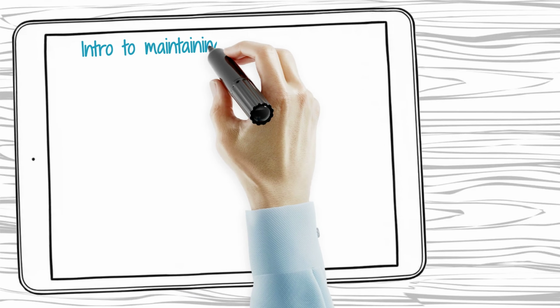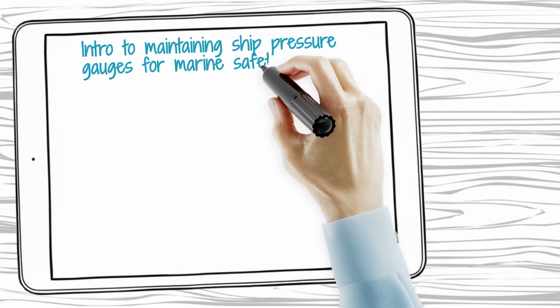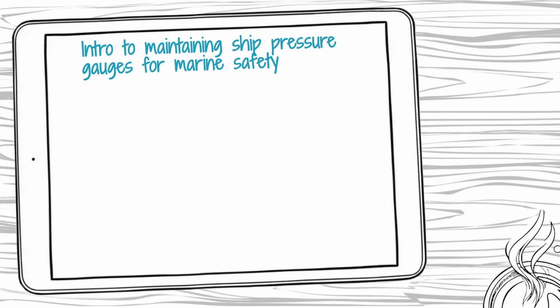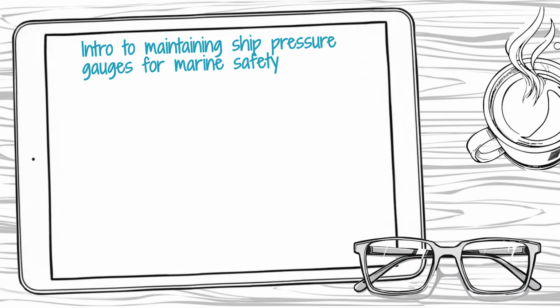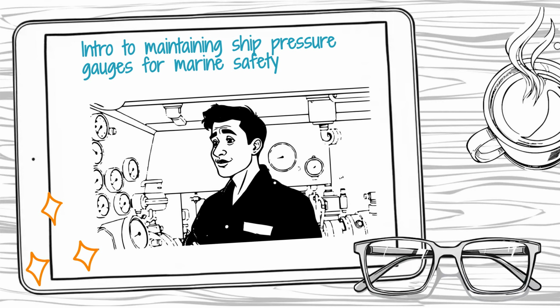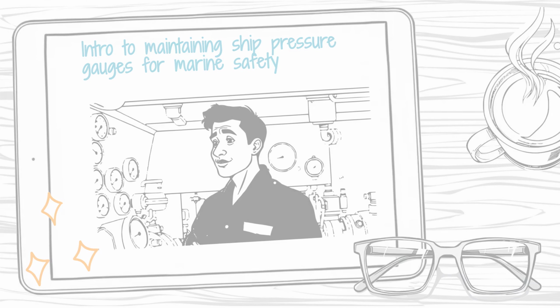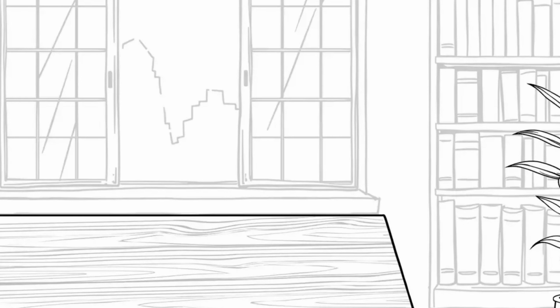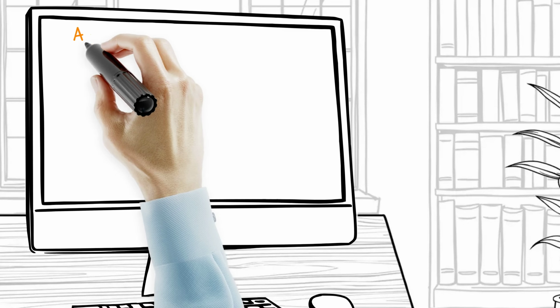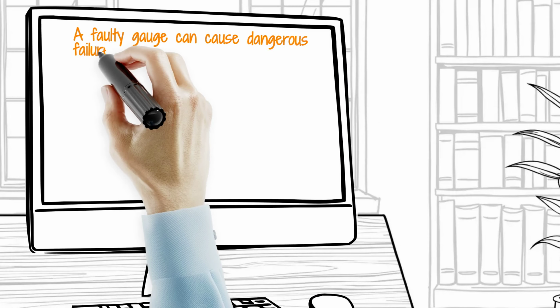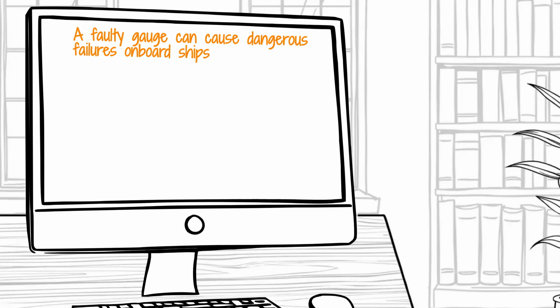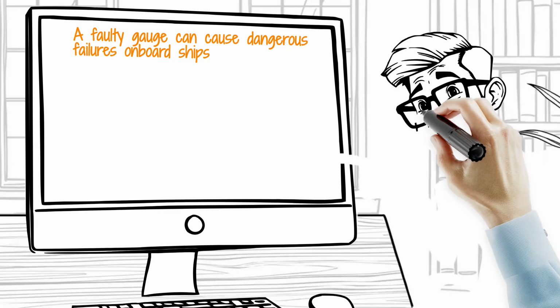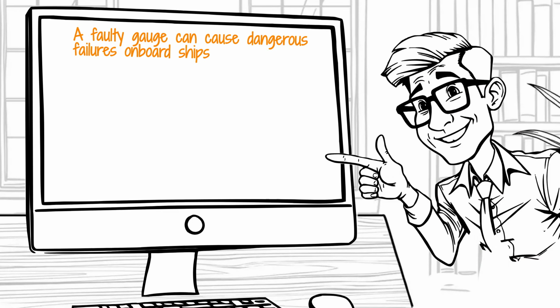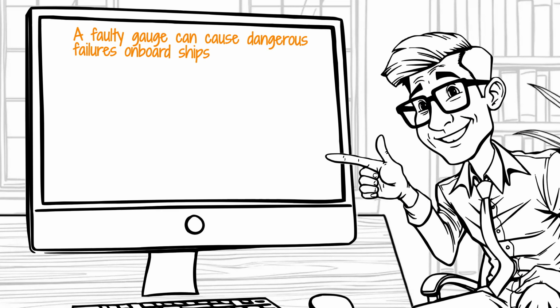Maintaining and calibrating your ship's pressure gauges is a fundamental task for every marine engineer because accurate readings are the only way to ensure that engines, boilers, and hydraulic systems operate safely. A faulty gauge can lead to catastrophic failure if it fails to warn you of a dangerous pressure surge or a loss of lubrication. To begin the maintenance process, you must first isolate the gauge from the system using the needle valve or gauge cock.